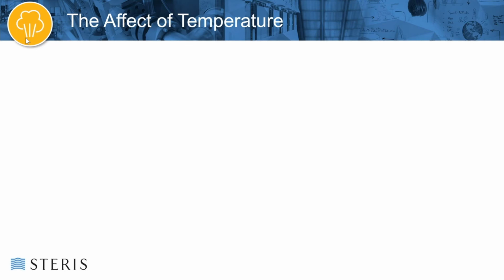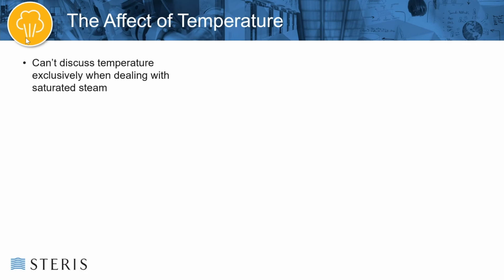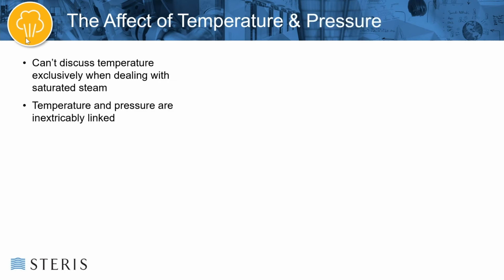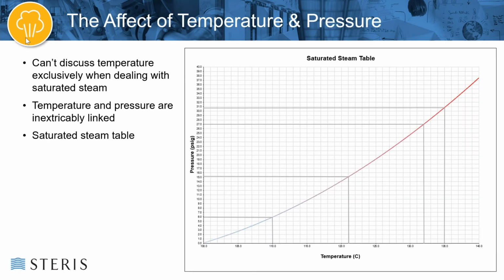So what is the effect of temperature on steam sterilization? Well, when we're dealing with a saturated steam environment, we can't discuss temperature exclusively. Steam temperature and pressure are inextricably linked. So they have what's called a saturated steam table, which is what I'm showing here. On the left, we have pressure. On the bottom, we have temperature. We can see that as temperature increases, pressure also increases. And this is a well-known engineering process that's well understood.